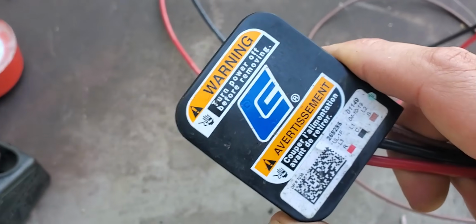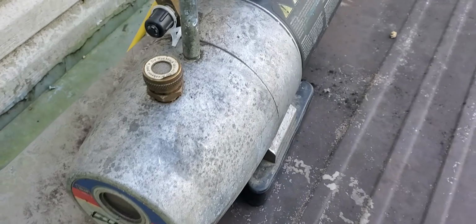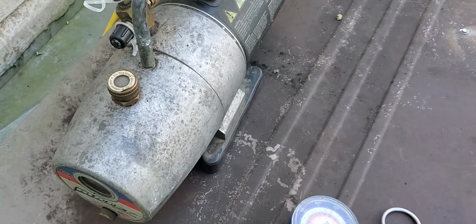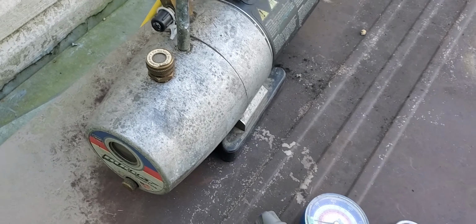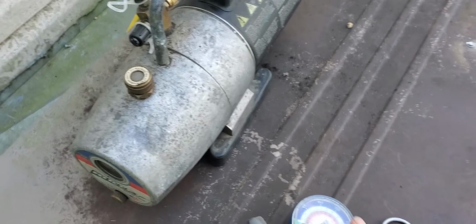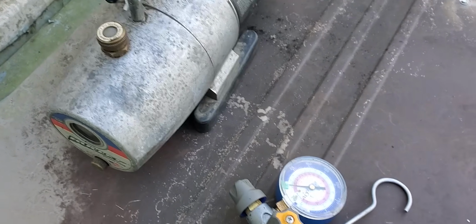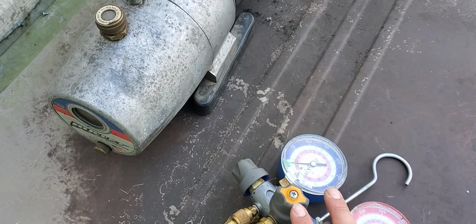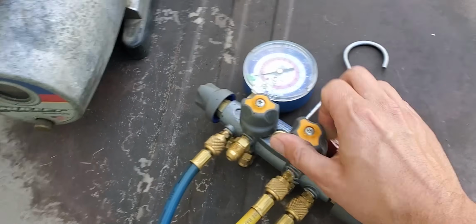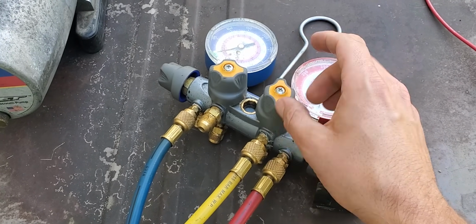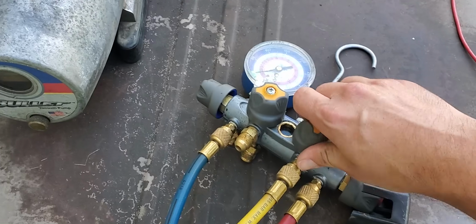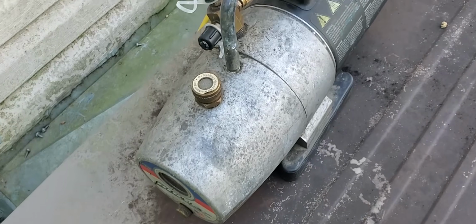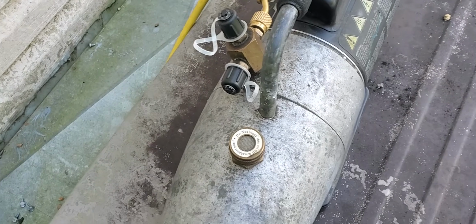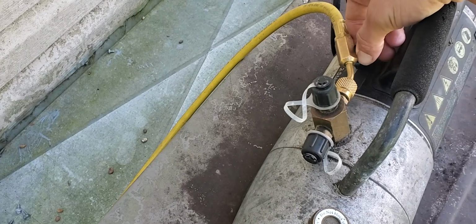I'm back. I got the plug for the compressor and sounds like it's done pumping down. Now, if you don't have a micron gauge, then a good way to know that the vacuum is working and it's vacuumed like it should be is you just basically turn off the manifold, go into the pump. You didn't hear it change sound, did you? Okay, shut it off, turn the pump off.